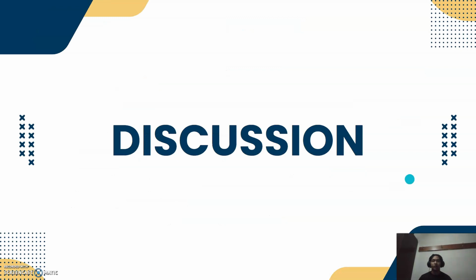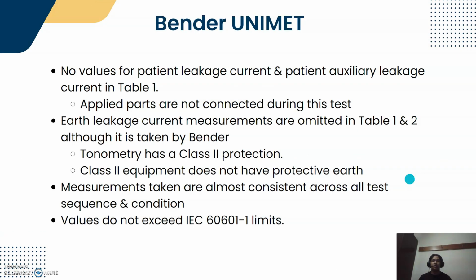Hi, I'm Unku, and now we will proceed to the discussion. For the Bender Unimet Analyzer, there are no values for patient leakage current and patient auxiliary leakage current in Table 1 because applied parts are not connected during this test. Earth leakage current measurements are omitted in Tables 1 and 2 although they are taken, because the tonometry has Class 2 protection and Class 2 equipment does not have protective earth. Measurements taken are almost consistent across all test sequences and conditions, and all values do not exceed IEC 60601 limits.